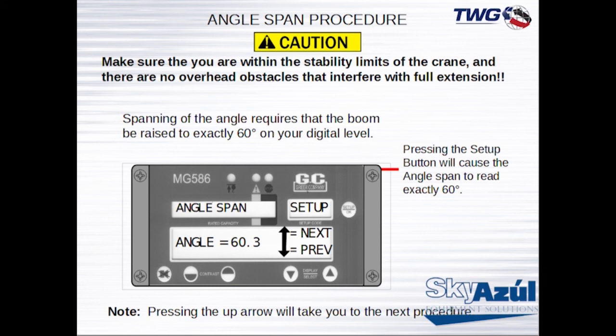So let's talk about angle span. It's the same kind of procedure, except we use a specific angle. After we set our zero, we use a specific angle, like exactly 60 degrees on your level. We raise the boom up to exactly 60 degrees, and probably you'll have some disagreement between this angle equals on your calibration process. When you press the setup button, it forces the system to say, okay, it's 60.0 - it puts that number in for you and confirms we're at exactly 60 degrees. Pressing the up arrow always takes you to the next procedure.